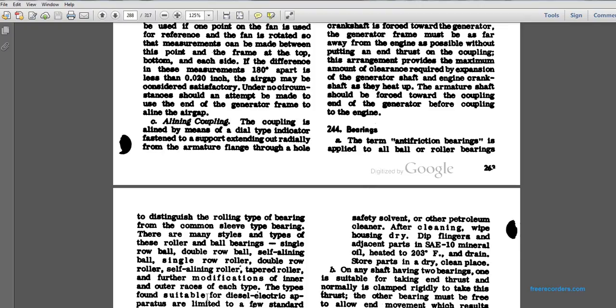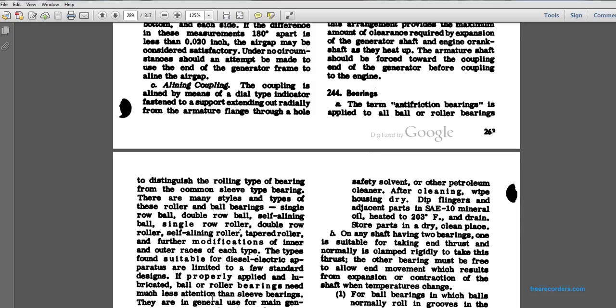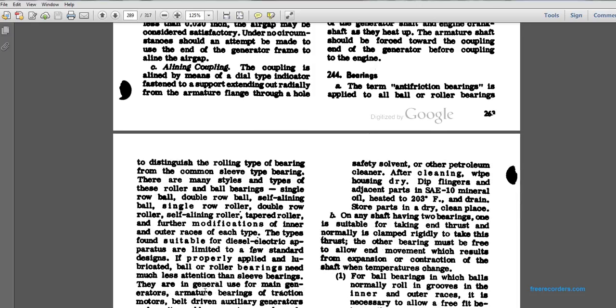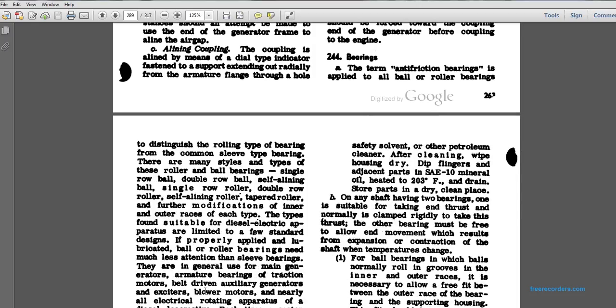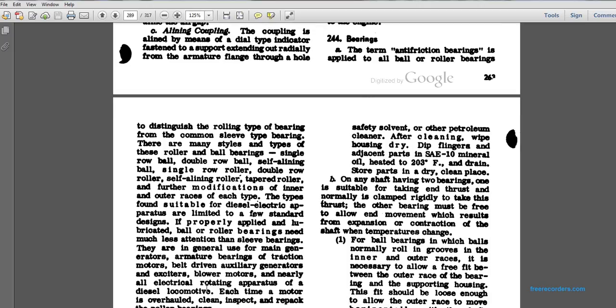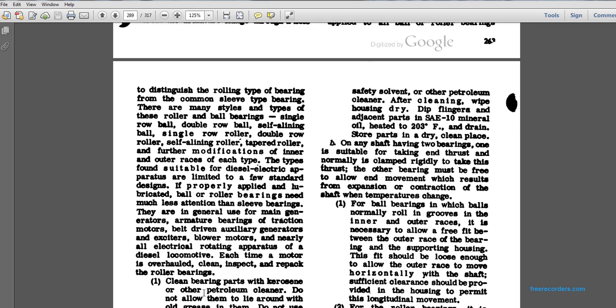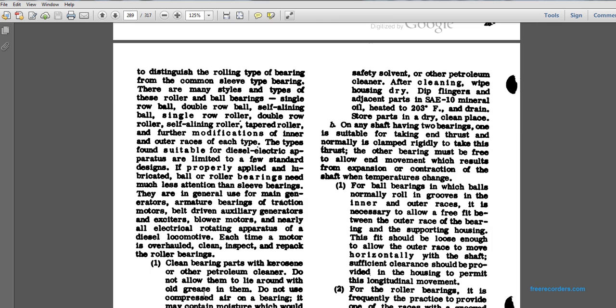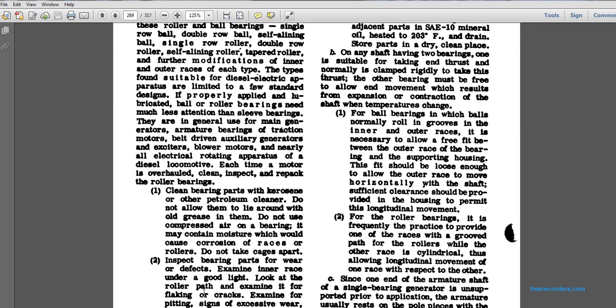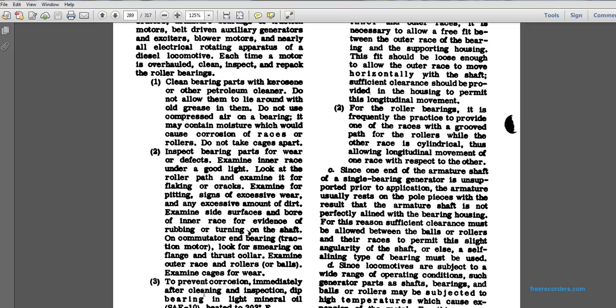The types suitable for diesel-electric apparatus are limited. If they are designed and properly applied, lubricated ball or roller bearings need much less attention than the sleeve bearings. They are generally used in the main generators and armature bearings and traction motors, belt-driven auxiliary generators, exciter blower motors, nearly all electrical rotating apparatus of a diesel-electric locomotive. Each time a motor is overhauled or cleaned or inspected, repack the roller bearings.